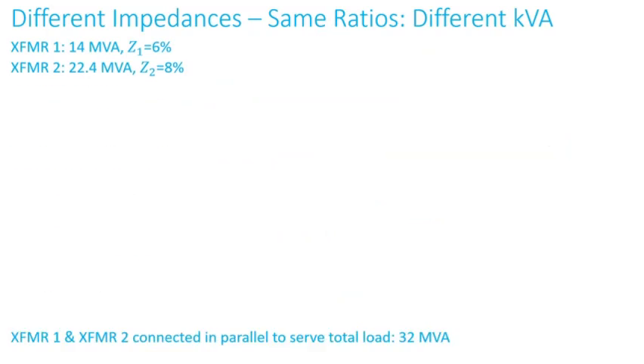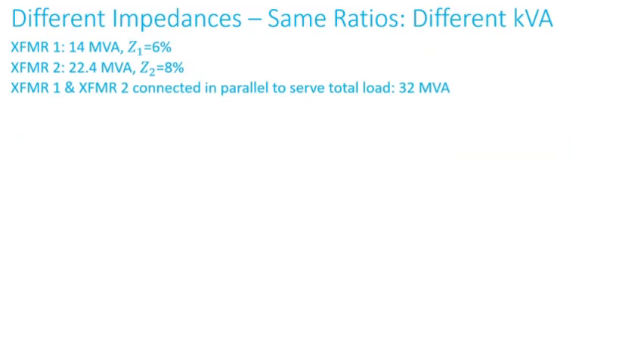Now we'll do the case where we still have different impedances and same ratio, but now different MVA ratings. Transformer one has a rating of 14 MVA with six percent impedance. Transformer two has a rating of 22.4 MVA with eight percent impedance. Both are connected in parallel to serve a load of 32 MVA.